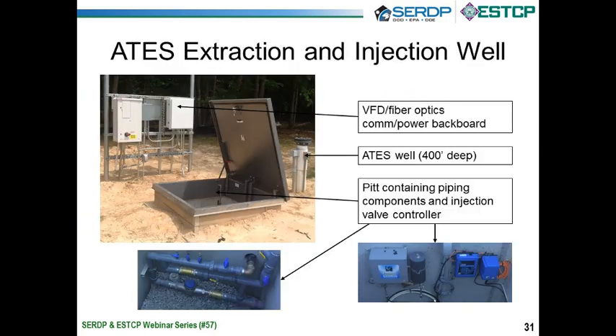Let me go back, I'm sorry. Up on the wall there are the variable frequency drives. On the left there, there's some electrical power, and on the back side of that is the communication box. We have fiber optic cable running the whole show. We don't want a lightning strike out here to get in the building and fry that. So we generally recommend fiber optic cable for all your communications outside. Fiber optics tie this back to the building.